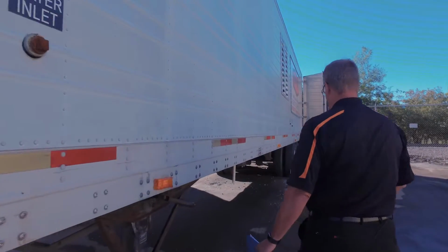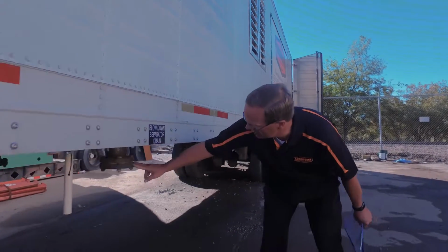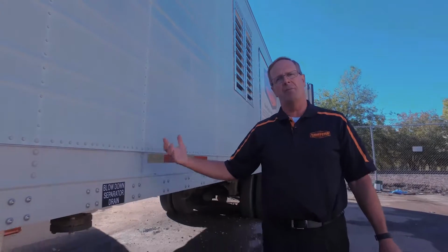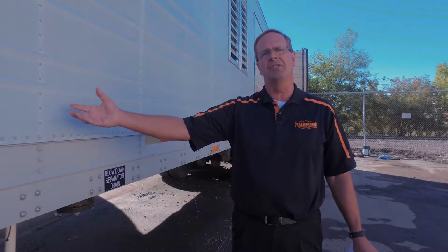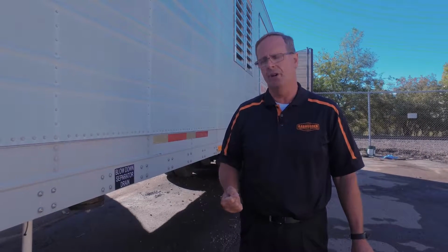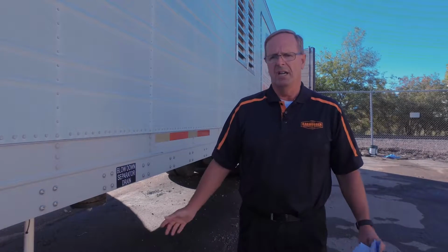Over here we have a connection which I want to point out is our blowdown separator drain. And as you can see underneath here, it's just a flange connection, and that takes care of our bottom blow as well as our surface blow on the boiler. So there's always going to be a maximum of 140 degree water coming out of there. We have a cooling valve inside that's going to make sure that it always is no more than 140 degrees by code. But that still is hot enough. We want to make sure it gets piped correctly to a floor drain or to a trench or something to keep somebody from getting hurt.